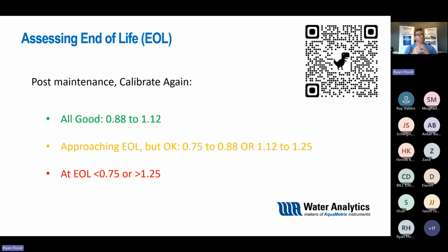If after you perform the maintenance, you've cleaned the sensor, replaced the salt bridge, and replaced the reference solution, and you're seeing values between just above 75% efficiency to 88% efficiency, or 112% to 125% efficiency, you can start to think that you're approaching the end of life. You still have time left on that sensor. It's not time to throw it out, but you may want to have one on your shelf ready to go as you move forward, or you may want to think about increasing your calibration frequency and maintenance frequency, because what it's indicating is that your sensor is starting to approach end of life.